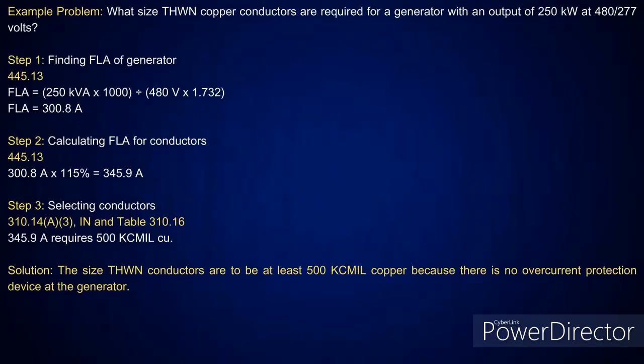Okay. Nice. Now here's one where I have a generator that has an output. So I need to get the full amperage for the output of that generator, and I've got a 250 kVA transformer. Take that times 1,000 to get it in VA form. I've got 480 volt. I want to get it on the primary there. So I'll take the 480 volt times 1.732, and that's going to give me 300.8 amps.